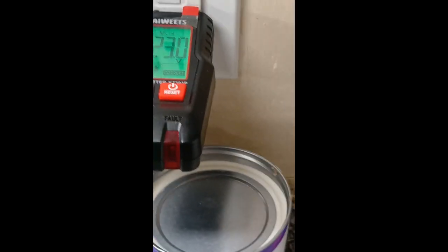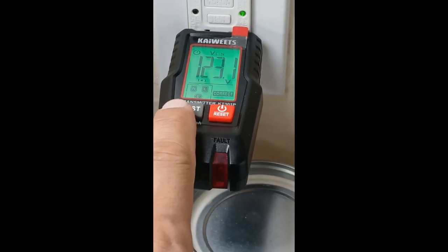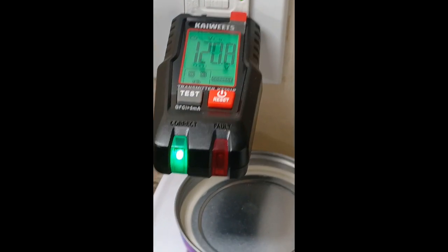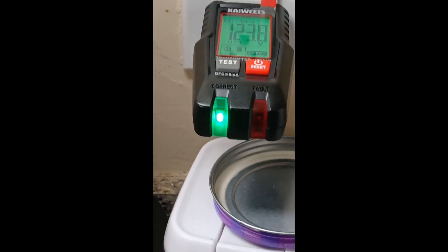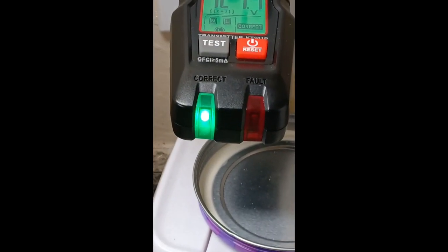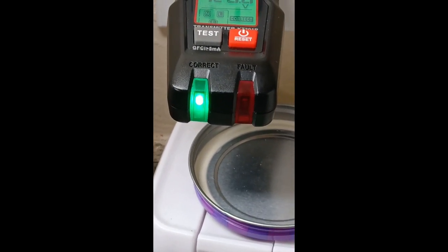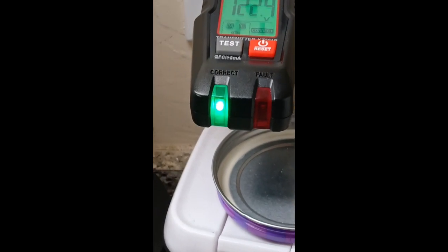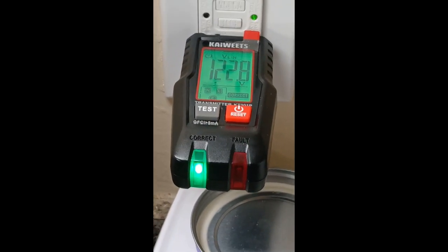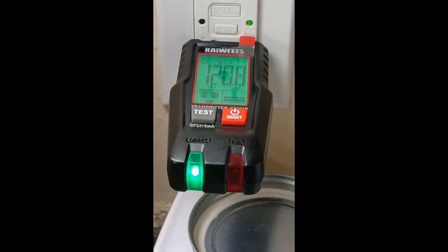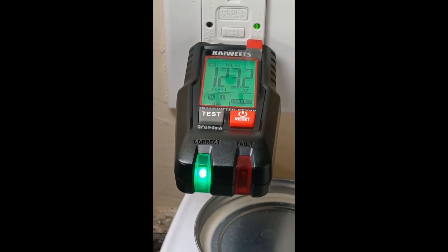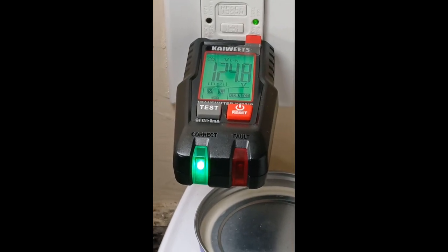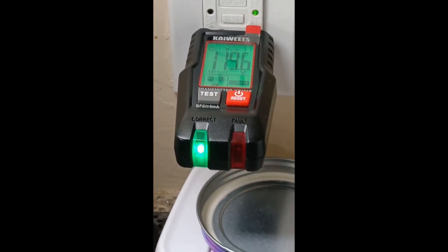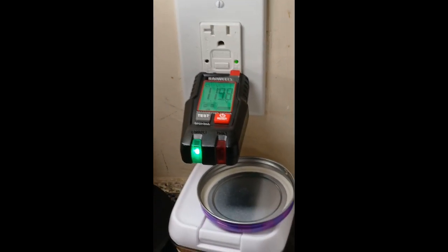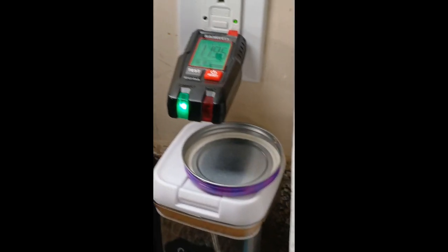All right, so it even shows you a little outline shape of the receptacle. Next up, as you can see, it also tells you if it's correct. You see the engravings, correct and fault. If there was a faulty GFCI or faulty device, it'll flash red. In this case, it shows a steady green. It's correct wiring, line to neutral voltage, and the little wiring signal icon keeps flashing. That means it's ready and transmitting a signal. It's ready to operate. But before we do that, we're going to try the test button for testing GFCI receptacles.